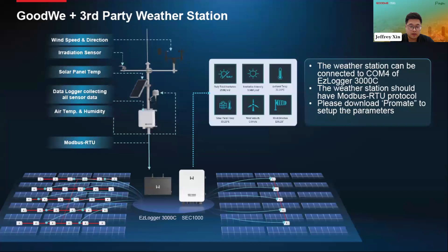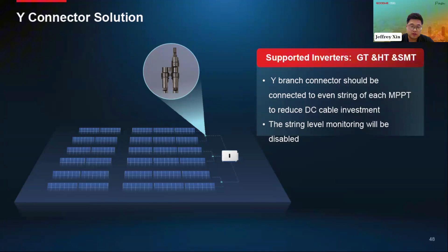On the data logger side, we provide a communication interface for the extra system, used for connecting to devices such as the weather station, transmitting required information via the Modbus RTU protocol and displaying it on the portal. Also, the Y branch connector should be connected to the even string of each MPPT to reduce DC cable investment.